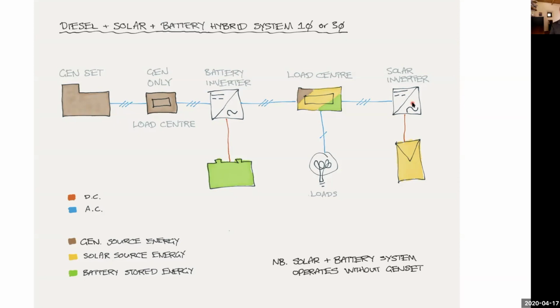And that's generally done by two strategies. The older strategy was using what's called frequency shift power control, invented some 20-something years ago, I think by SMA, where the battery inverter would deliberately slightly change the frequency. Very small, just a 1.5 hertz maximum variation. And that frequency shift was a way of communicating to compatible solar inverters that they must reduce their power output.